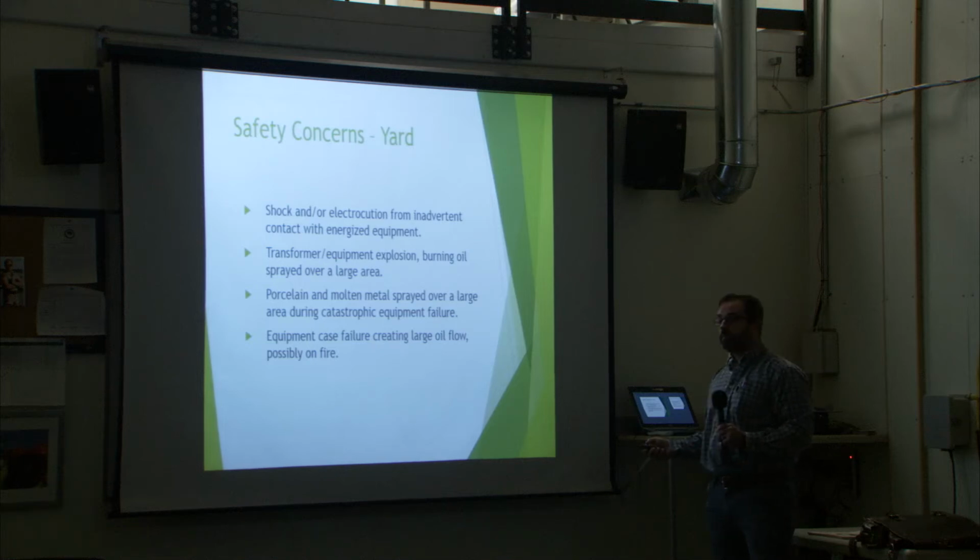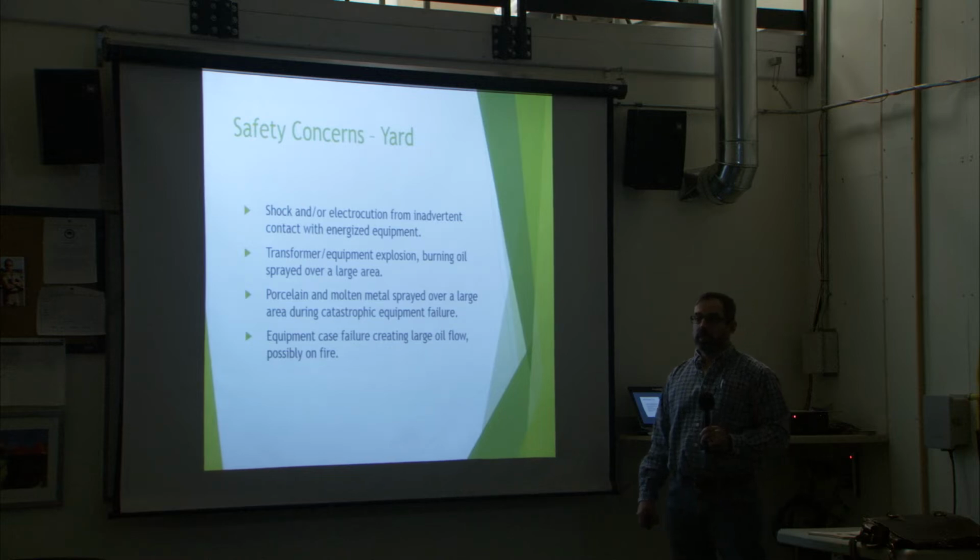Has anybody been part of a regulator blowing up? When I was an apprentice, over there, it's quite the mess. Oh yeah. Quite the mess. We had one at Amos Sub that let go, because they build up so much pressure in there. It had oil sprayed all over all the bus work. I mean, there's only a couple hundred gallons of oil in a regulator.